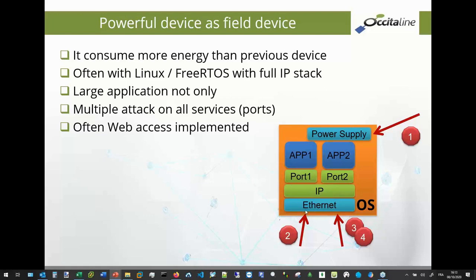If you use on field a big device with a large application, with an operating system like Linux or FreeRTOS, in fact, you are more sensitive to attack. Why? Because in fact you have a full IP stack implemented, and you can support many protocols such as FTP, SSH, web services, BACnet, or what you want, or Modbus, and so on. And in fact, you have a lot of doors open for this device.